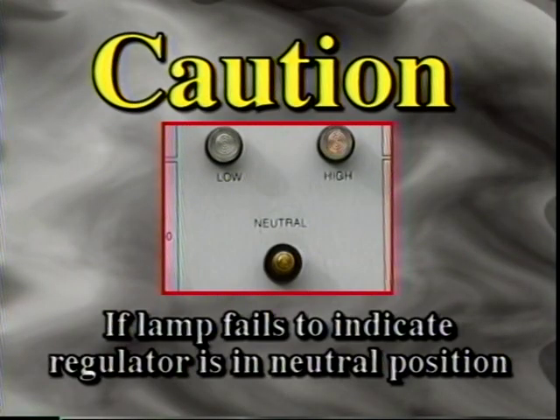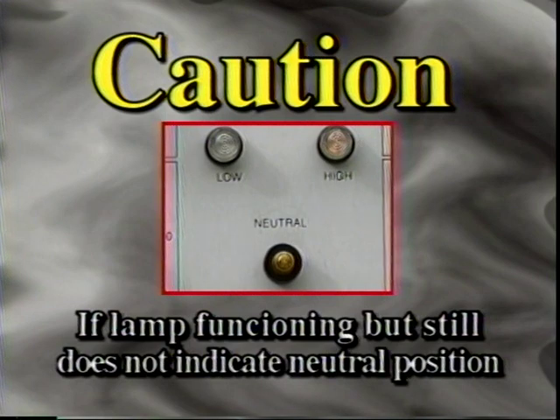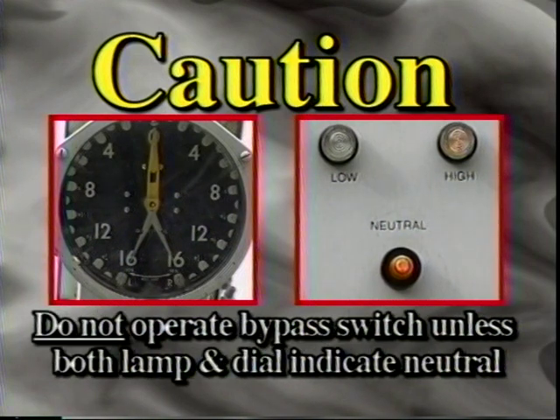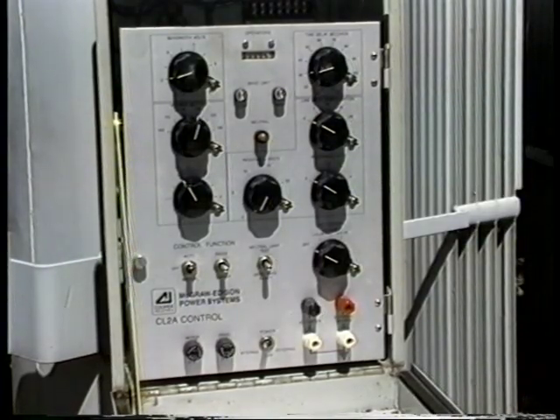Also, if the neutral lamp fails to indicate that the regulator is in the neutral position, first check to ensure the lamp is functioning correctly. If the lamp is functional but still does not indicate neutral positioning, the source voltage will need to be de-energized in order to remove the regulator from service. We repeat: unless your company has specific instructions for this situation, do not close the bypass switch unless both the drag-hand indicator and the neutral lamp indicate neutral, or the source voltage has been de-energized. Once the source has been de-energized, close the bypass switch, open the source-side disconnect switch, open the load-side disconnect switch, and restore power to the circuit.